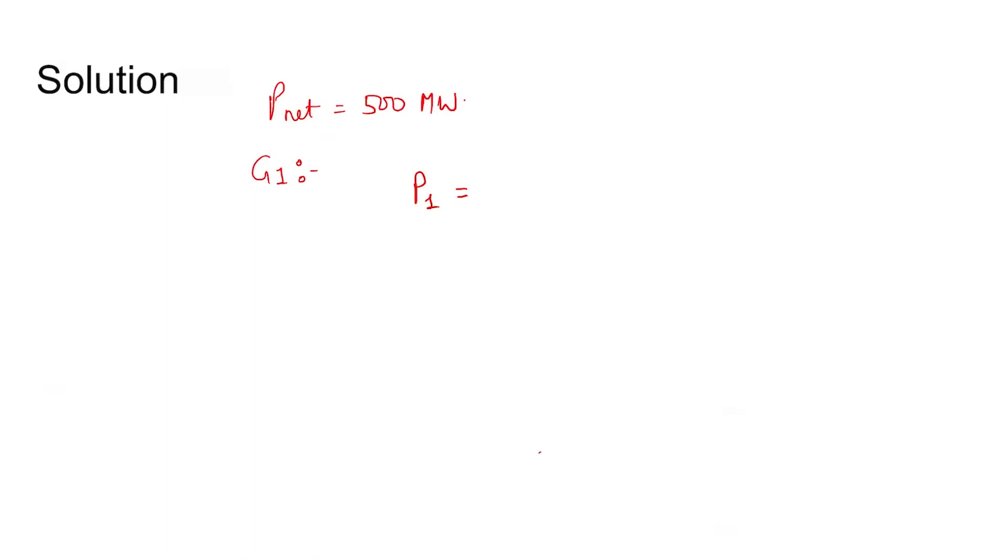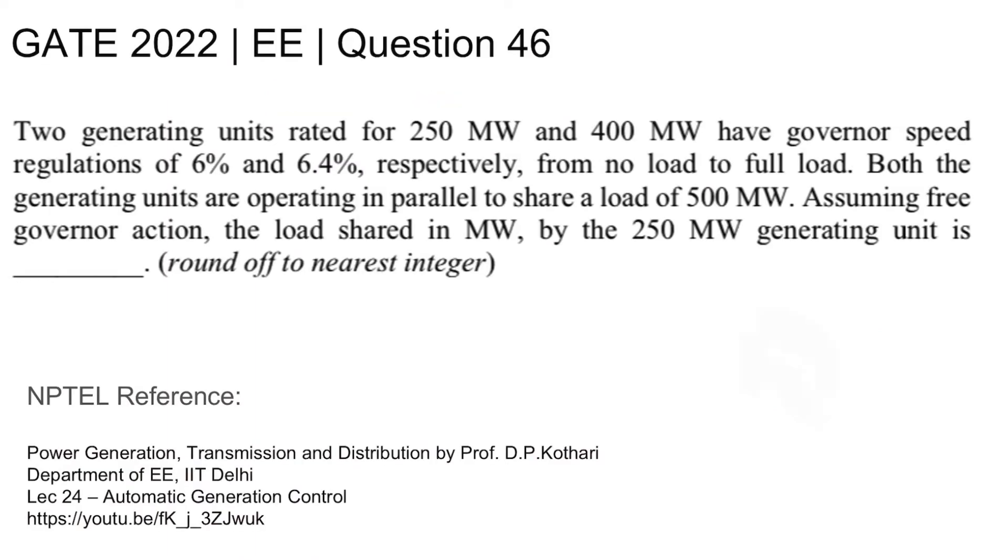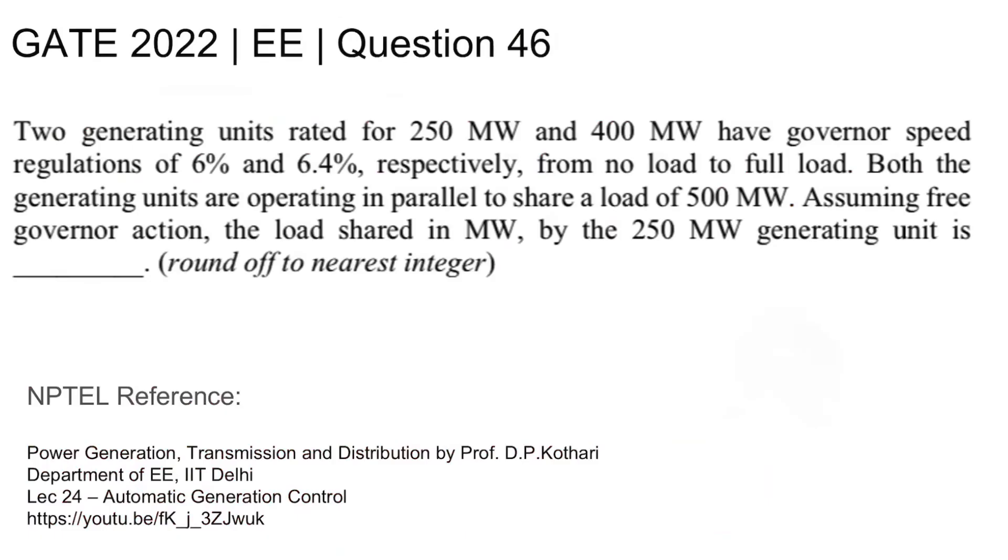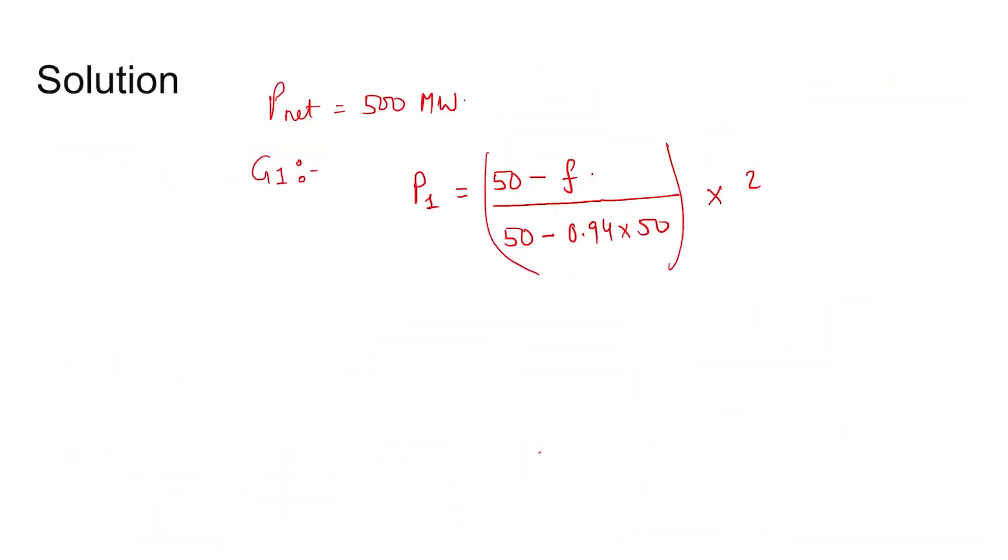The power generated by one equal to no load frequency, which is given in the question, no load frequency which is 50 hertz let us assume, minus operating frequency divided by no load minus full load frequency. Six percent drop we see, so 0.94 times 50, because six percent has been reduced. So this times the full load capacity of the generator one which is 250.